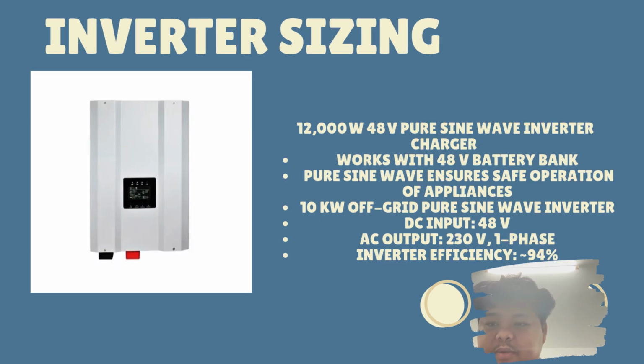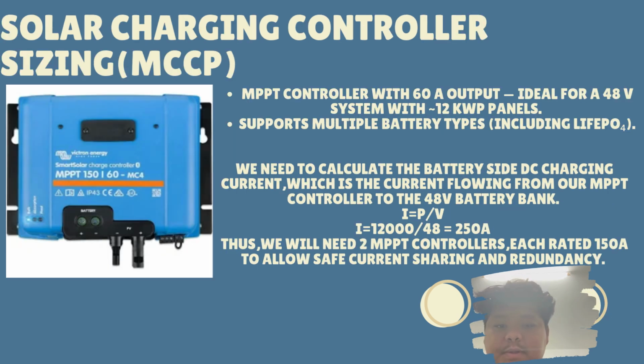For the inverter sizing, we are using a 12,000 watt 48 volt pure sine wave inverter charger. It works with a 48 volt battery bank, and pure sine wave ensures safe operation of appliances. The DC input is 48 volts, the AC output is single phase 230 volts, and the efficiency is 94%. This is for the solar charge controller sizing, MPPT. An MPPT controller with a 60 ampere output is ideal for a 48 volt system with 12 kWp panels. This MPPT also supports multiple battery types, including the lithium iron phosphate battery that we are using.